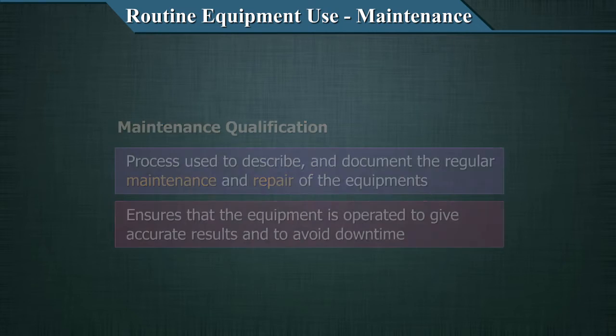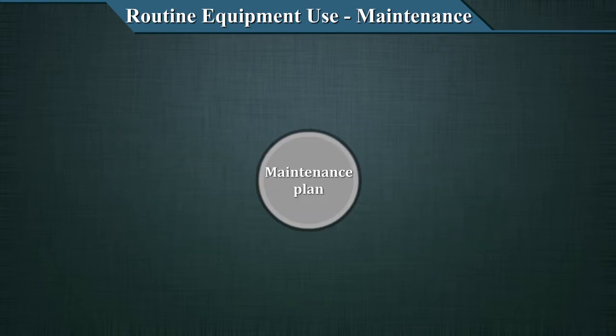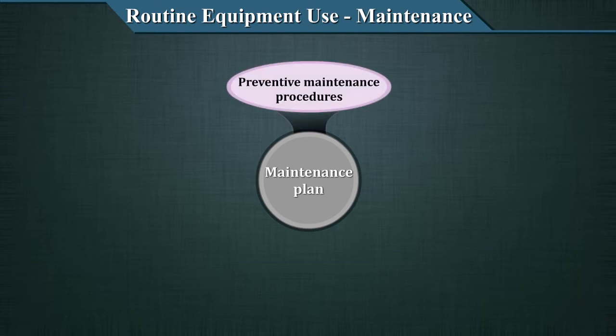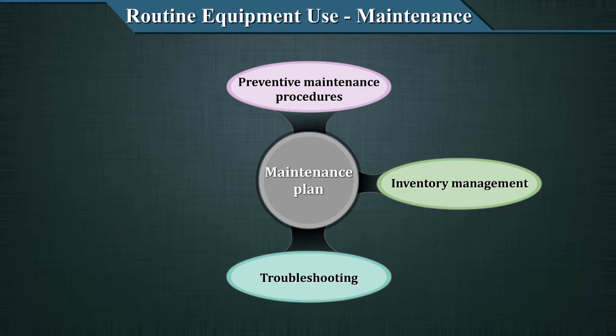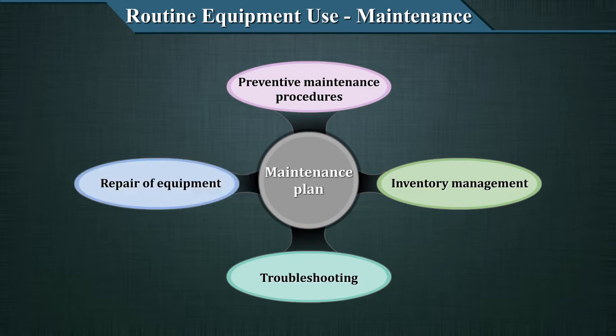Every MQ starts with a maintenance plan. A maintenance plan should include Preventive Maintenance Procedures, Inventory Management, and Troubleshooting and Repair of the Equipment. When we say Inventory Management, it is mostly about the spare parts inventory that we are talking about.